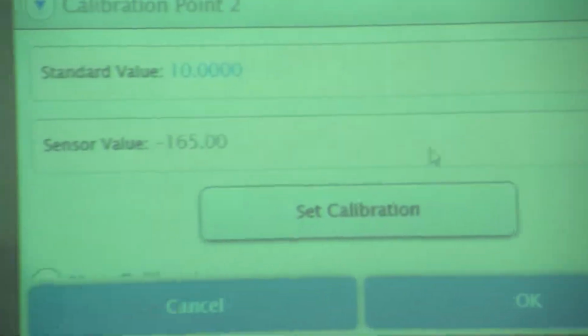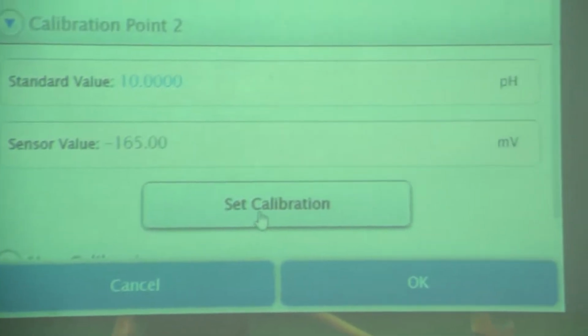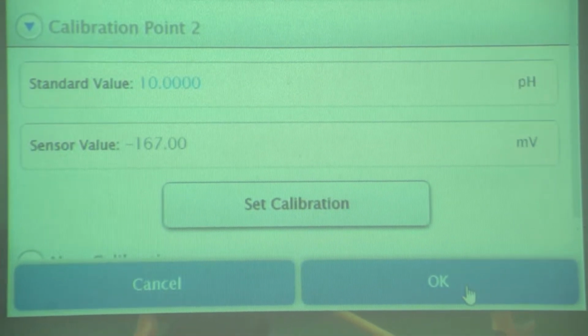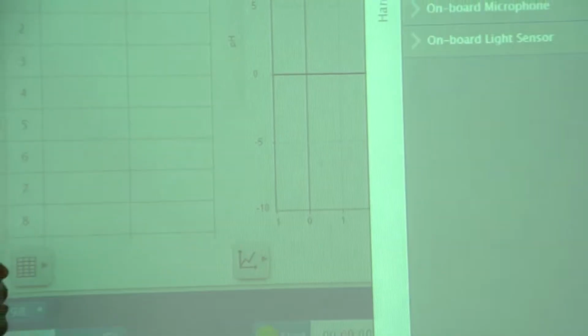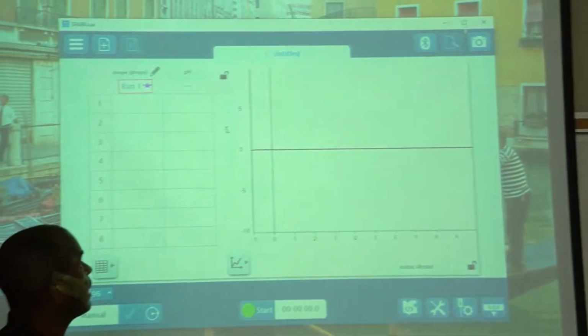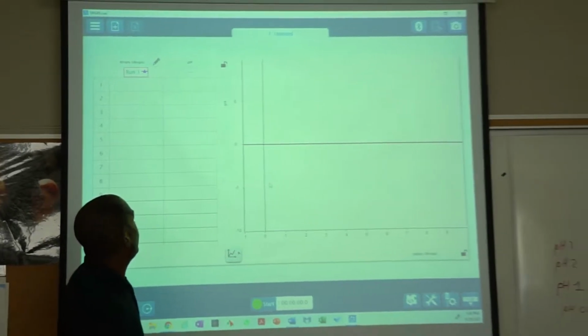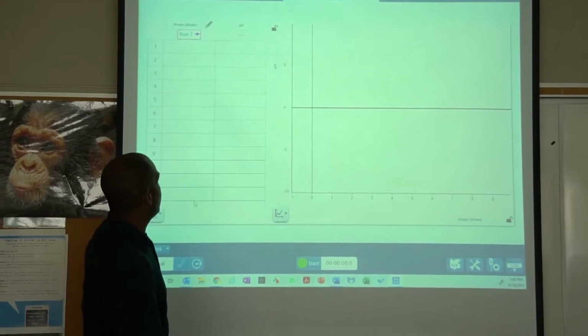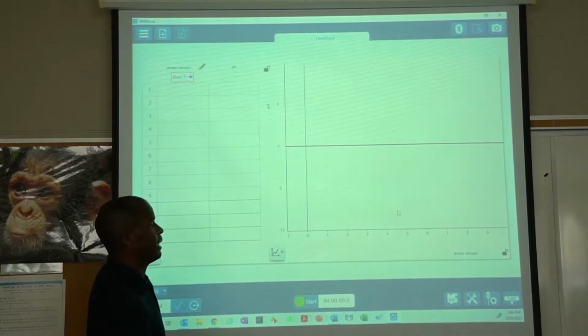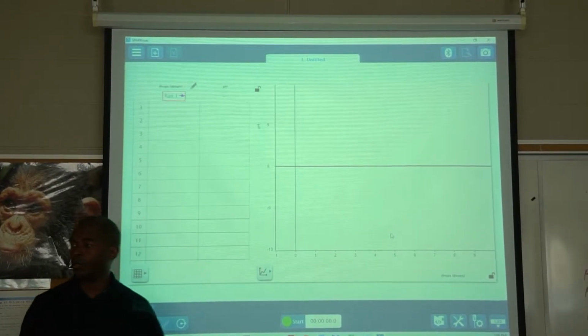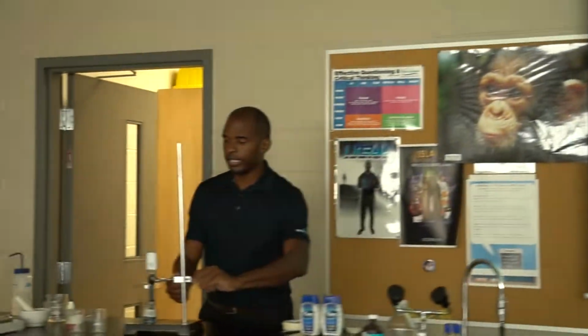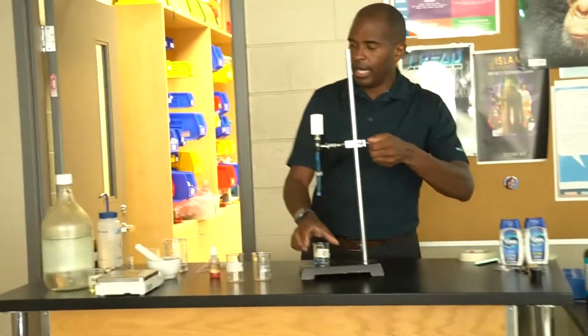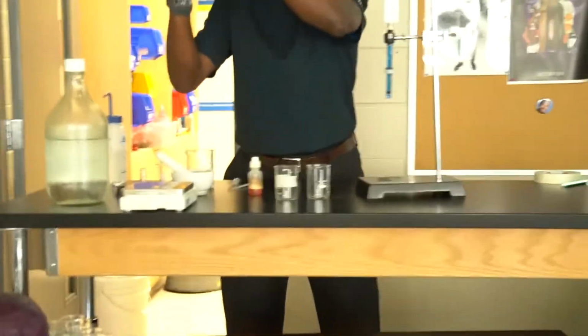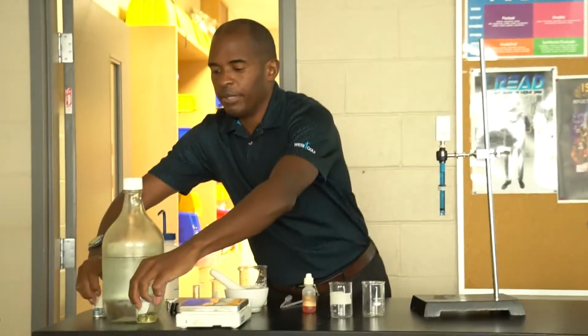I confirm that my standard value says 10. I let it sit for about 10 seconds, which I've done. I hit set calibration. I click OK. I click this little close arrow. I can maximize my screen. And now I have a data table, and I have this graph. All right, so it's ready to go. I'm going to take my pH sensor out of the buffer. I'm done with my buffers, so I'm going to give them to somebody else if they need them. I'm not using them anymore.